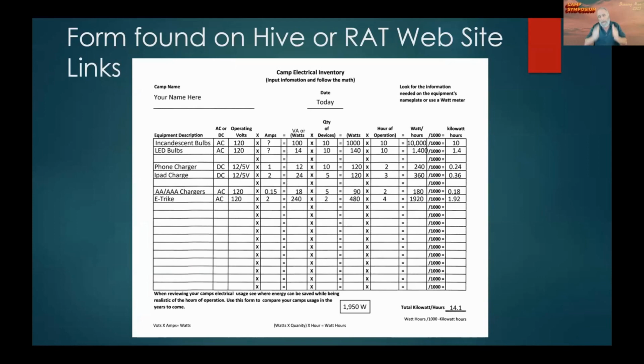If we use that column of watts, we can size our generators, and it'll help you identify what you need for your inverters. Then we take it a step further and want to know the watt hours for our solar and wind systems. Here we multiply the watts times the hours of operation - another piece of cake.